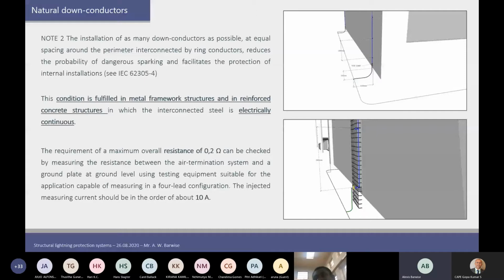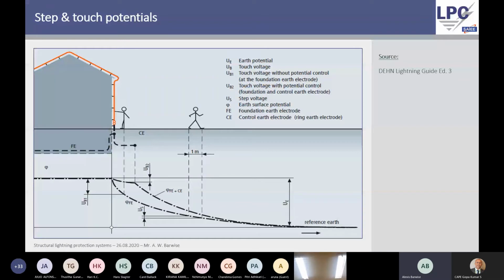It states here that the condition is fulfilled when the metal framework of structures or the reinforced concrete of these structures are electrically continuous, meaning if we want to use the reinforced concrete, the I-beams, or any sheet that even goes down, like the IBR sheeted warehouses nowadays, where the roof and the walls are all made up of the sheet that is conductive. It says it's a great concept, use it. Just ensure that there is continuity from the roof all the way down to the earth. Obviously, because we want to conduct the currents down to the earth sink system itself. And there we state that the requirement is at least a 0.2 ohm value, which I think everyone knows, that when you do a bonding test, at least one wants to achieve 0.2 ohms to ensure that there is a physical connection.